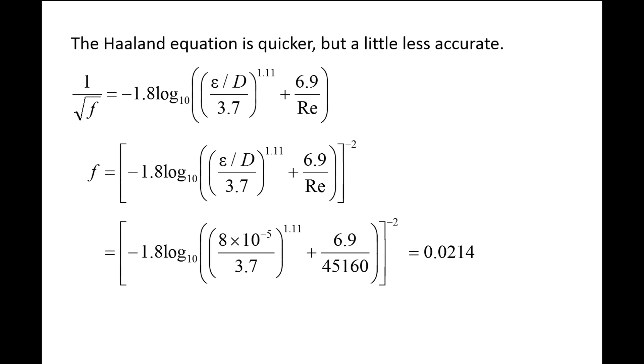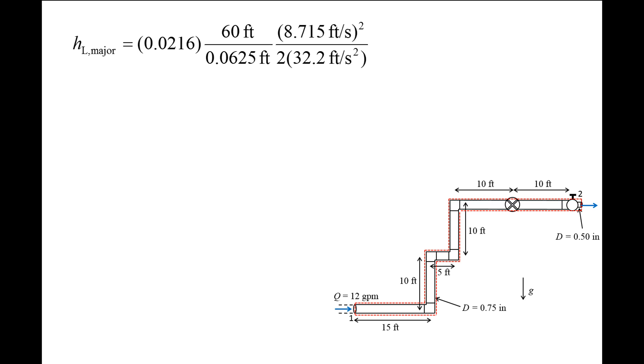On your own, check that the friction factors obtained using the Colebrook equation and Haaland equation are close to the value obtained using a Moody chart. Plugging in the values for the friction factor, pipe length, pipe diameter, and average speed into the major loss equation, we find that the major head loss is 24.46 feet.